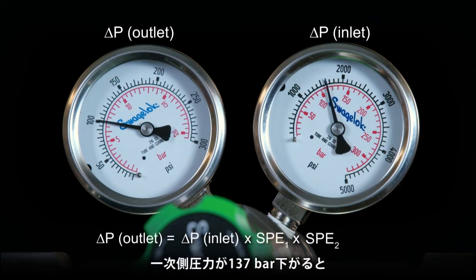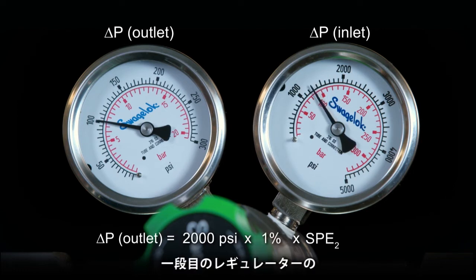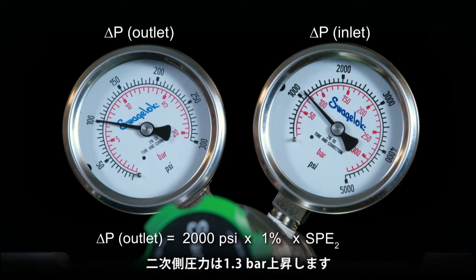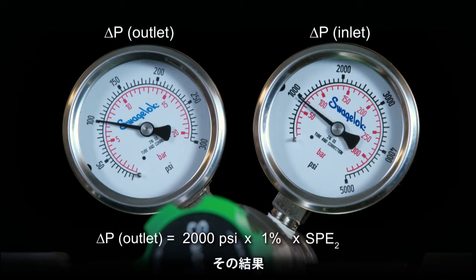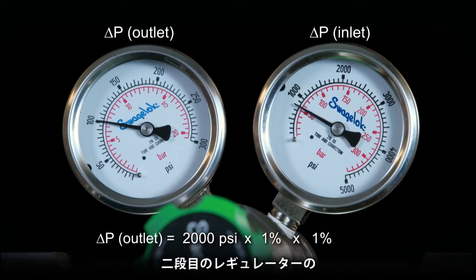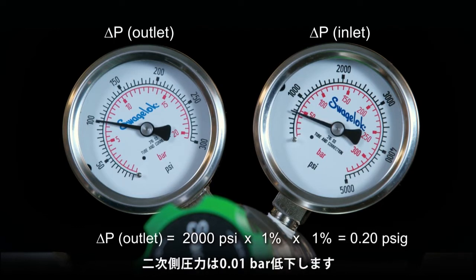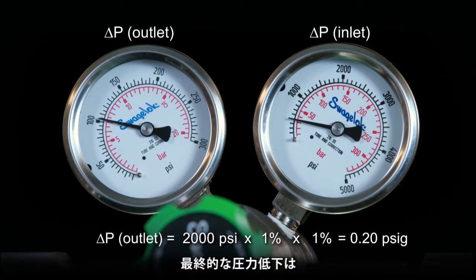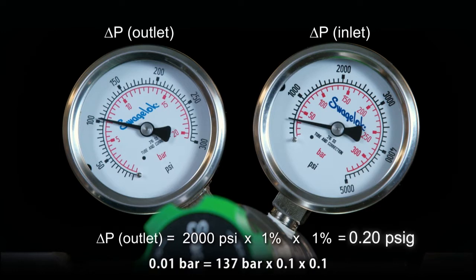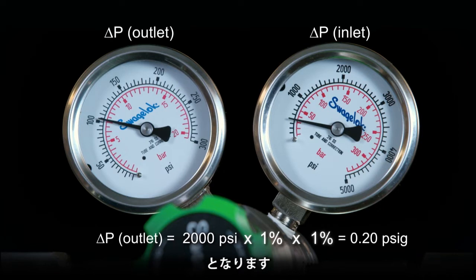With a 137 bar or 2000 psig inlet pressure drop, the first-stage regulator will experience a 1.3 bar or 20 psig increase in outlet pressure. As a result of that increase, the second-stage regulator will experience a 0.01 bar or 0.20 psig decrease in outlet pressure. The net result is a minimal pressure decrease that is only 0.01% of the initial cylinder pressure drop. 0.01 bar or 0.20 psig equals 137 bar or 2000 psig times 1% times 1%.